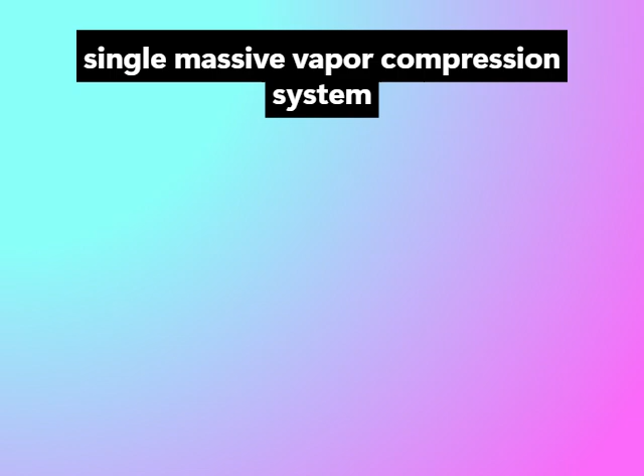Let's track the energy flowing through that plant. Let's assume we input 250 kilowatts of electrical work to drive the central compressor. Okay, 250 units of electrical input. And let's say the evaporator side absorbs 1,000 units of thermal energy from the water to chill it down to 10 degrees. So our refrigeration COP is what we want, 1,000 units of cooling, divided by what we paid, 250 units of work. 1,000 divided by 250 gives us a refrigeration COP of 4.0. For every kilowatt of electricity purchased, the plant gets 4 kilowatts of cooling power.